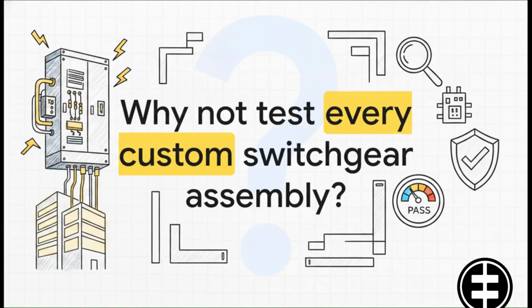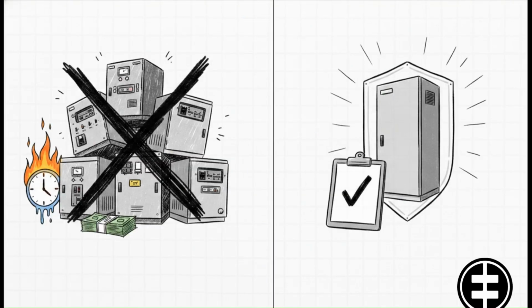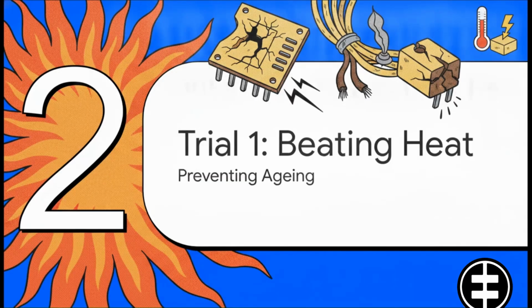Now, knowing that these custom assemblies control so much destructive power, you might be wondering, why not just test every single custom unit built before it actually gets installed in a building? I mean, it seems like common sense, right? Well, the reality is that pushing every single custom layout to the point of destruction is way too costly and time-consuming. These are highly complex, often entirely bespoke systems. So instead of testing every tiny variation, manufacturers put representative standard assemblies through these rigorous type tests. By definition, a standard assembly only contains equipment layouts and wiring configurations that have already undergone and, crucially, survived these specific type tests. Moving right along to Section 2, Trial 1, Beating Heat and How We Prevent Premature Aging.